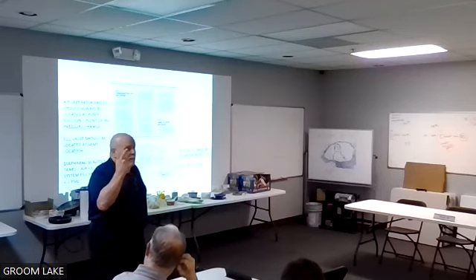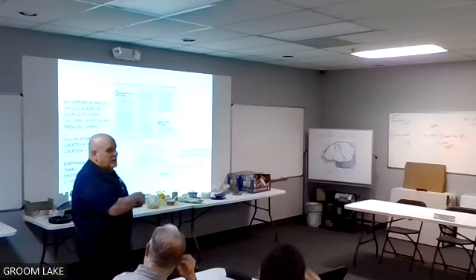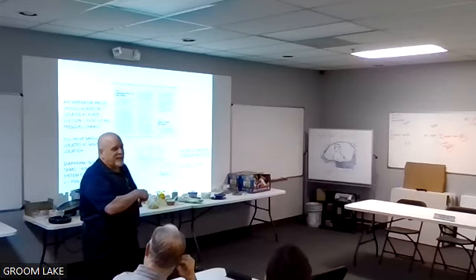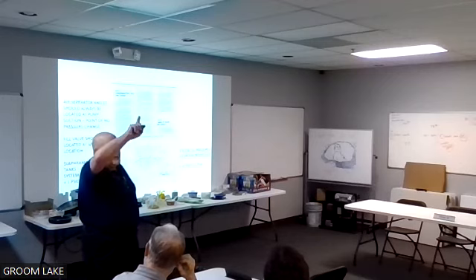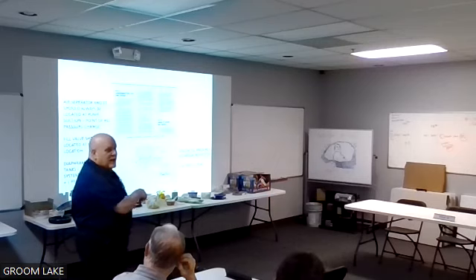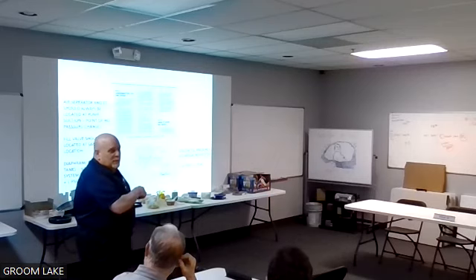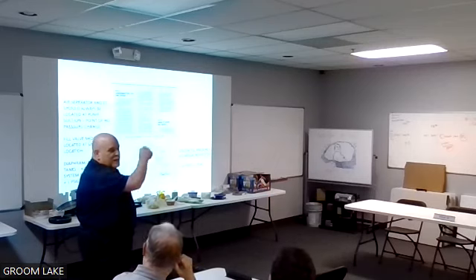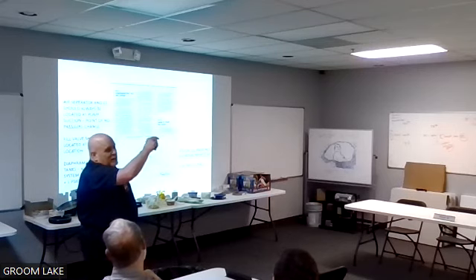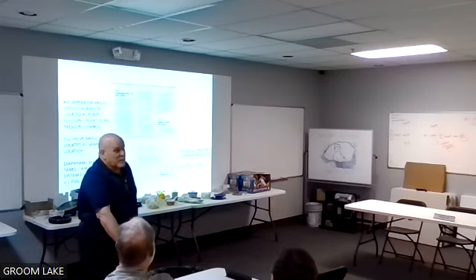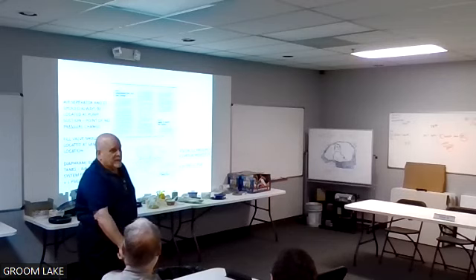Because now instead of me having to do a 250 PSI ASME tank, expensive. If I put all my equipment on the top floor, I only have 12 pounds up there. Now I can use 125 pound ASME. I don't lose my 12 pounds of fill pressure because of gravity. If I put 12 pounds on the top floor, by the time it comes all the way to the bottom, it's going to be at 200 PSI.